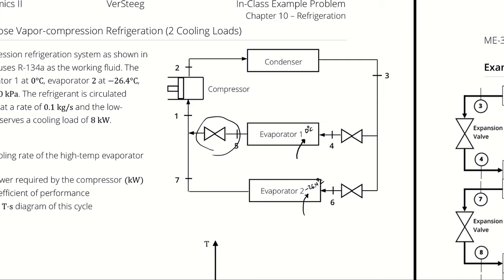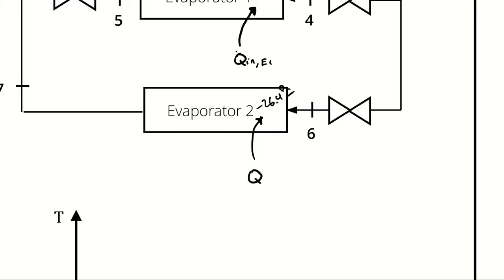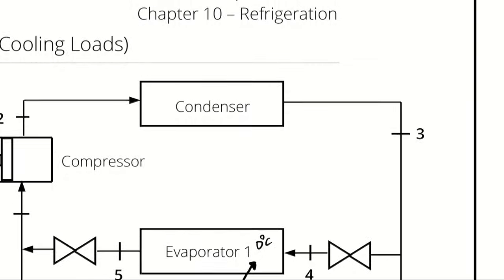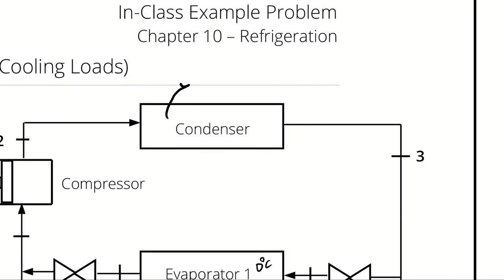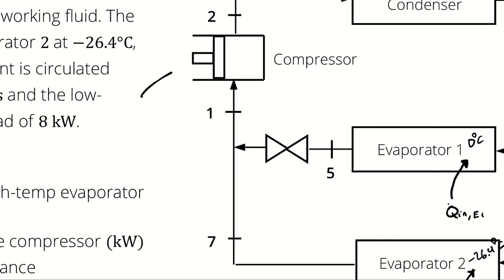We have a high pressure, true of states 1, 2, and 3; a medium pressure, true of states 4 and 5; and a low pressure, true of states 6, 7, and 1. I have two different sources of q_in: the rate of heat absorbed by evaporator 1 (q_in_e1) and by evaporator 2 (q_in_e2). The heat rejected by the condenser is q_out, and there is only a single source of work input — our compressor.